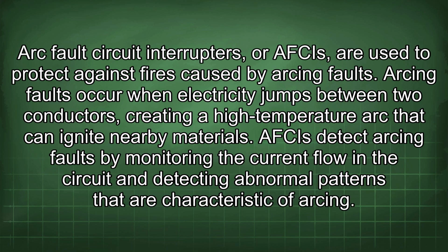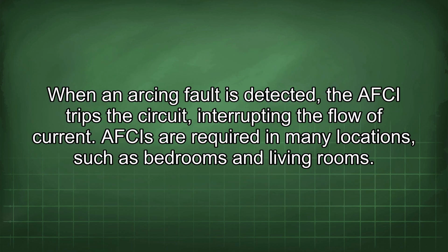Arc fault circuit interrupters, or AFCIs, are used to protect against fires caused by arcing faults. Arcing faults occur when electricity jumps between two conductors, creating a high-temperature arc that can ignite nearby materials. AFCIs detect arcing faults by monitoring the current flow in the circuit and detecting abnormal patterns that are characteristic of arcing. When an arcing fault is detected, the AFCI trips the circuit, interrupting the flow of current. AFCIs are required in many locations, such as bedrooms and living rooms.